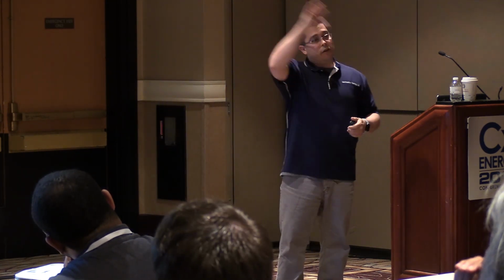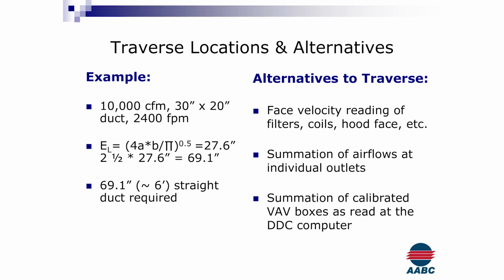That's one way. Obviously, it's a lower static drop through the unit than having the return duct associated with that, but it's a way to at least establish a volume for what's going through that fan. Another way to do it is to traverse the coils. If we can actually get inside the unit, we can do a Velgrid traverse of a cooling or a heating coil, and that'll also give us a total flow going through the unit. So those are two examples of how to establish a traverse even in the absence of straight duct.